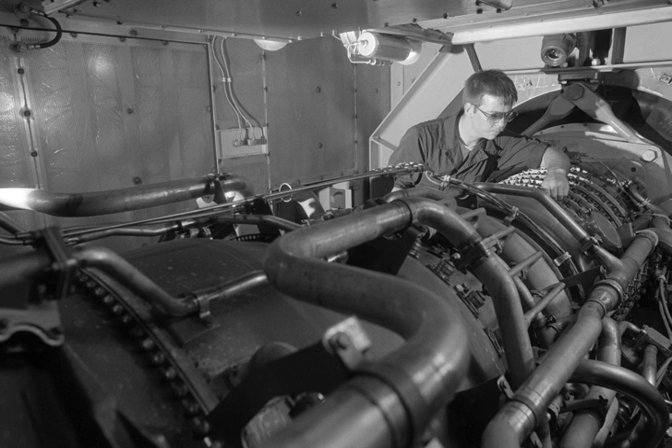When coupled with an electric generator, the LM2500 Plus delivers 29 MW of electricity at 60 Hz with a thermal efficiency of 38% at ISO conditions. The latest fourth-generation LM2500 Plus G4 version was introduced in November 2005 and delivers 47,370 SHP with a thermal efficiency of 39.3% at ISO conditions.